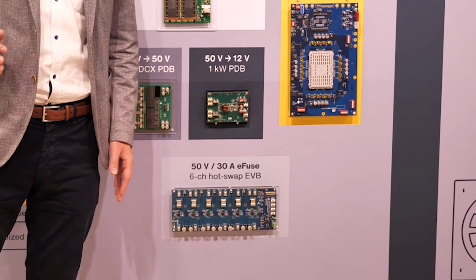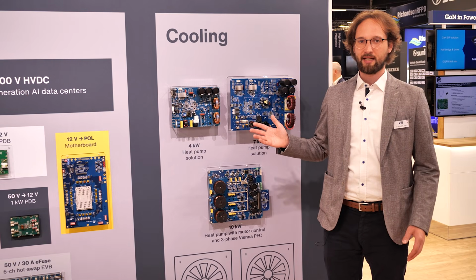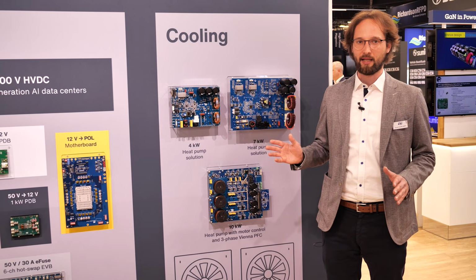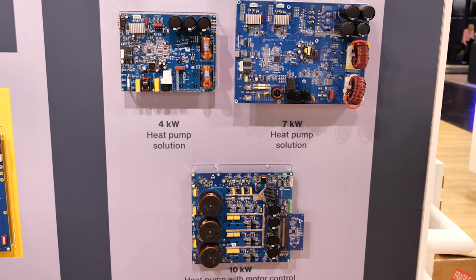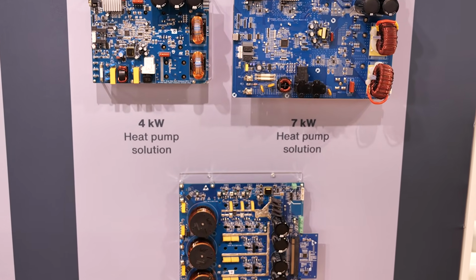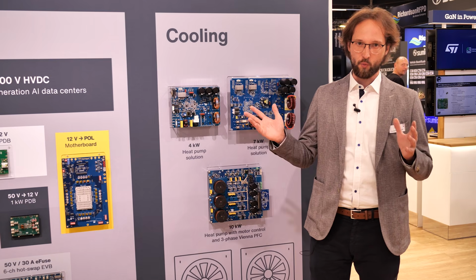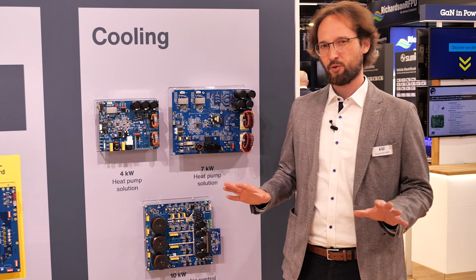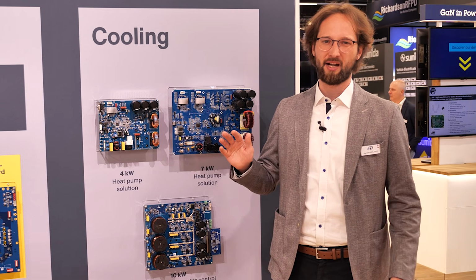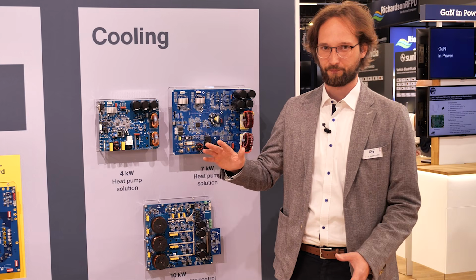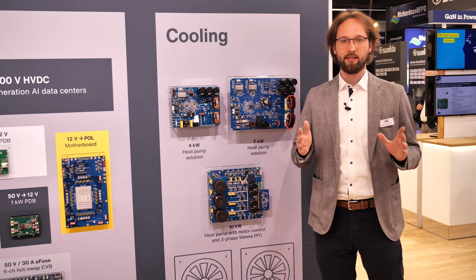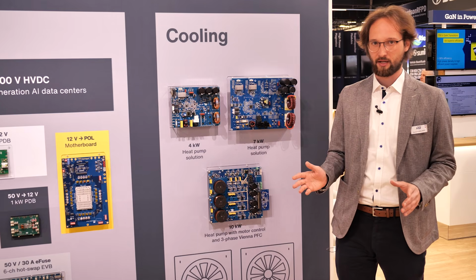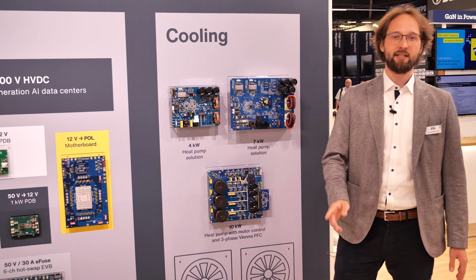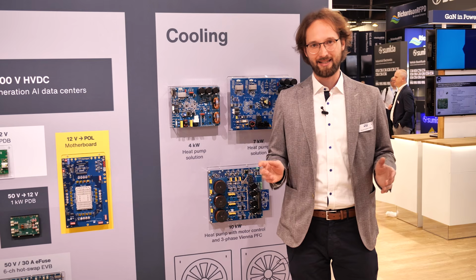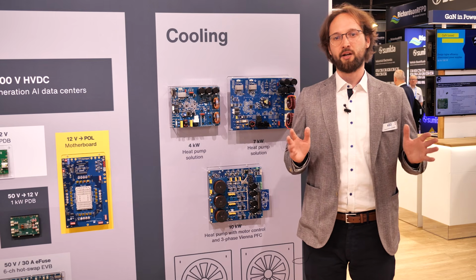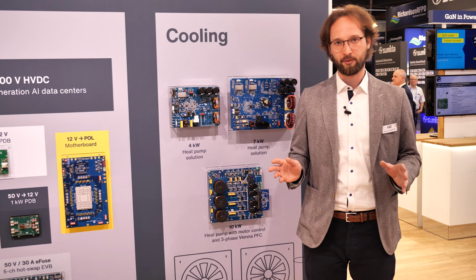What gets missed in discussion about AI servers is that cooling has become a problem. AI rack heat output scales with input power. The cooling system must grow with it. Conventional air cooling reaches a harsh ceiling somewhere around 50 kilowatts per rack. Past that, the industry moves to liquid loops driven by heat pumps. These are more environmentally friendly than the evaporative systems, which are known for their high water consumption.